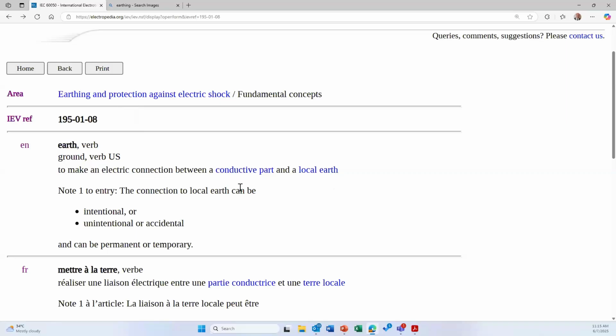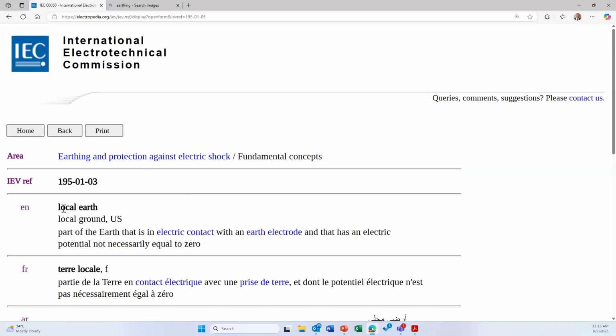Here, the definition has totally changed. To make an electric connection between a conductive part and local earth. The meaning of local earth, or local ground in America, is part of earth that is in electric contact with an earth electrode and that has an electric potential not necessarily equal to zero. The previous idea was conventionally taken as zero, whereas in the new definition, the potential of the earth electrode need not be equal to zero. Now, you see local earth.